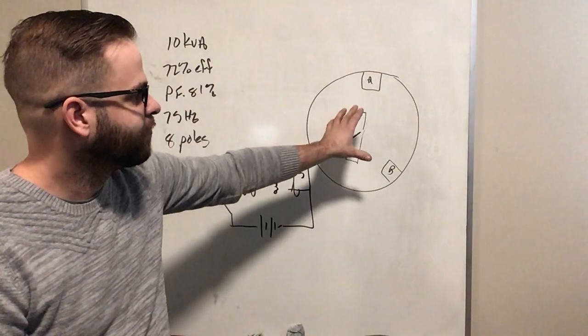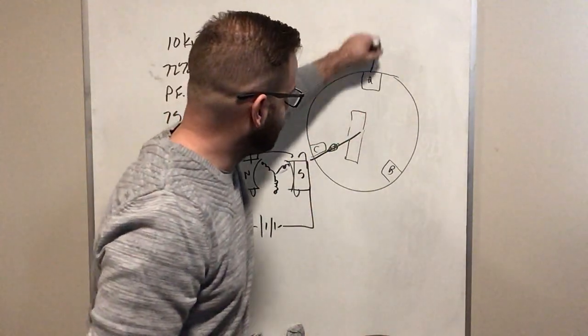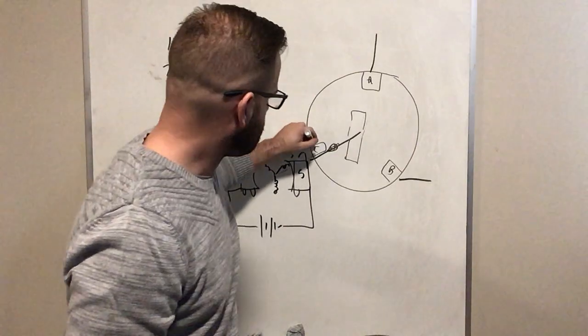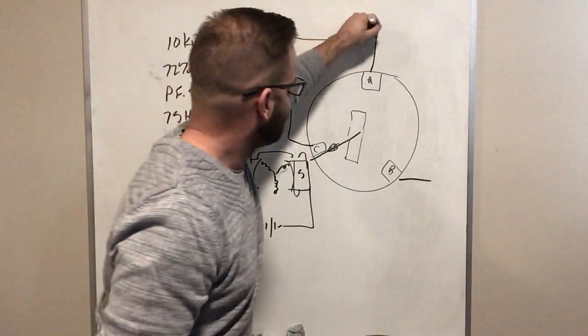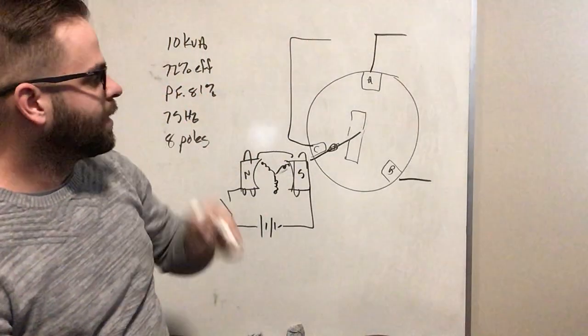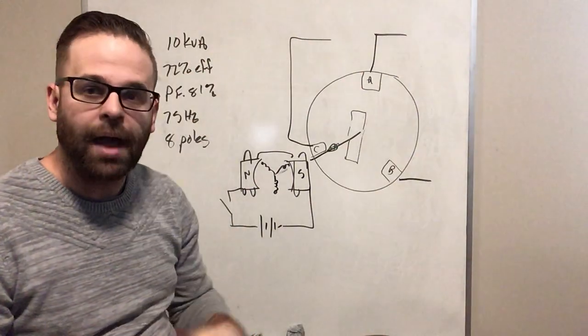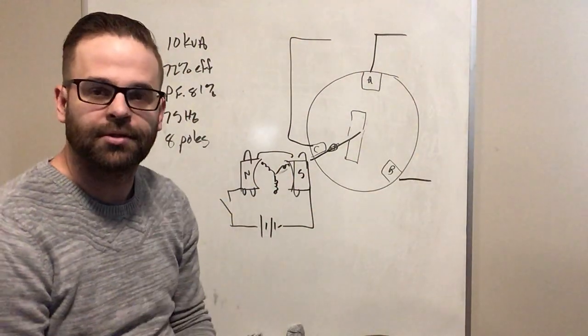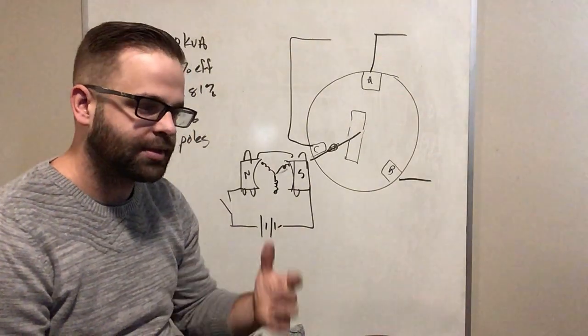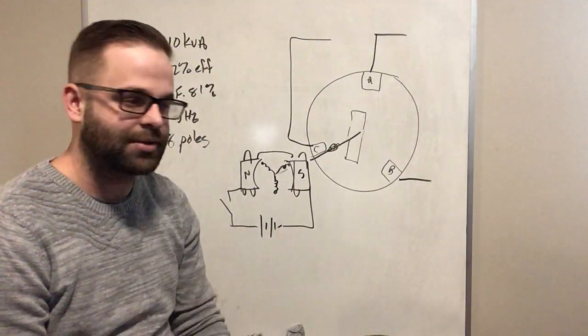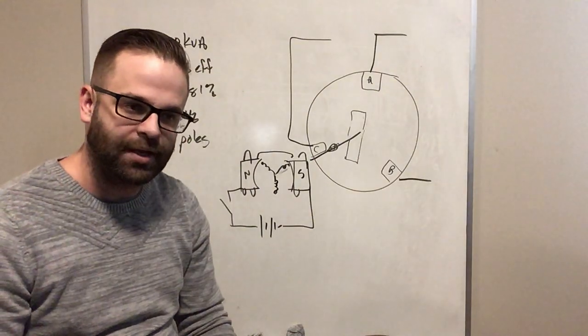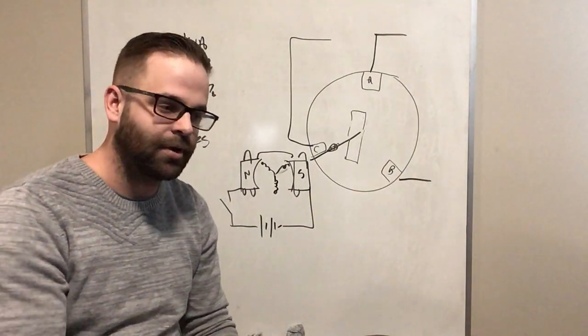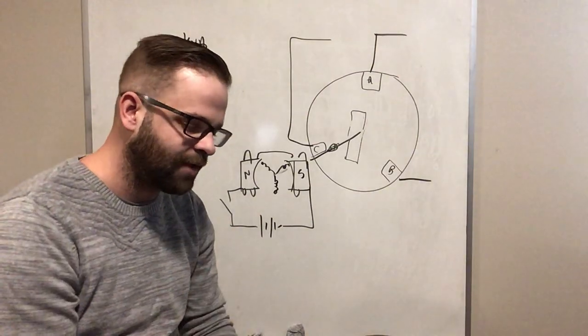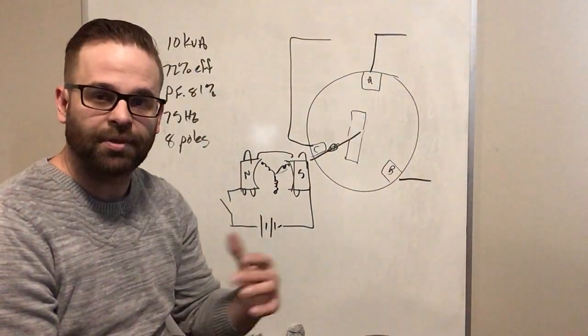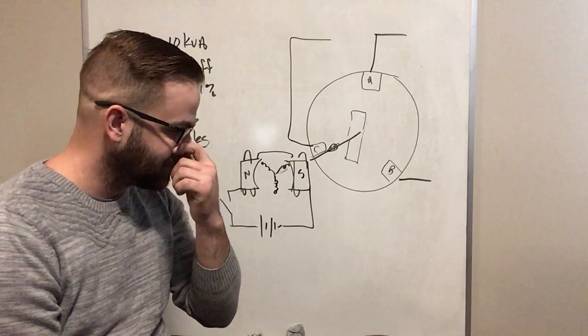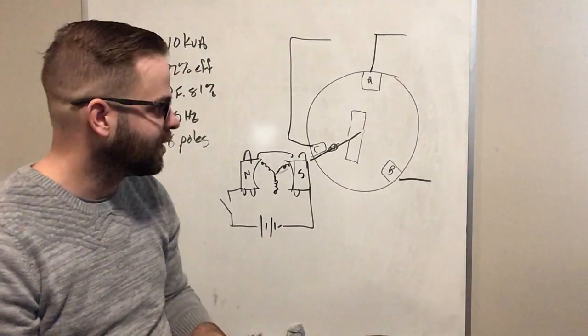So we've got our shaft, and we've got phase A, B, and C. How do we supply a three-phase voltage to a three-phase motor? Well, the simple answer is just supply power to it. Either turn on your motor starter or turn on your switch, whatever you have to do to supply it. As soon as I supply voltage to a three-phase motor, I get a rotating magnetic field.